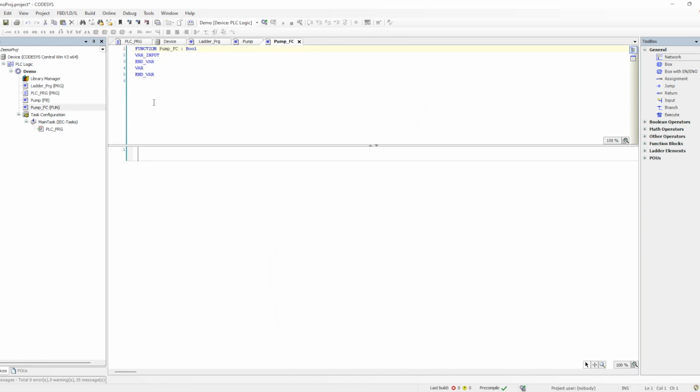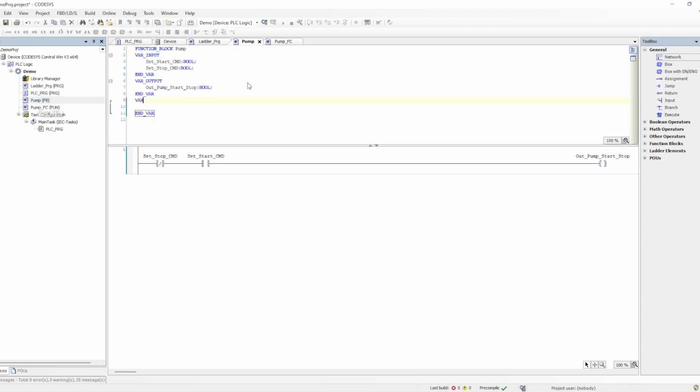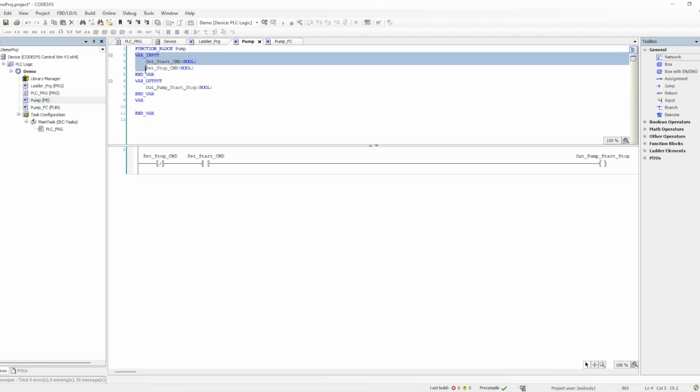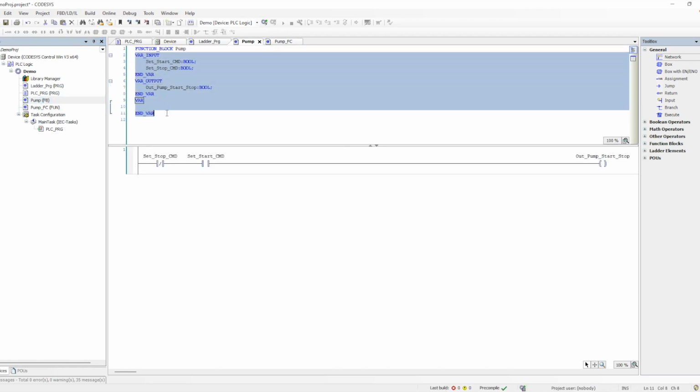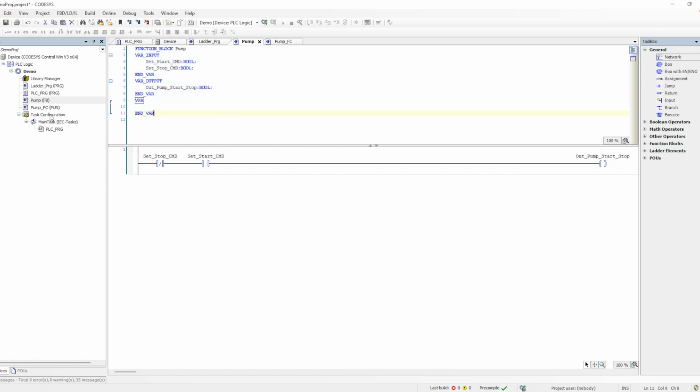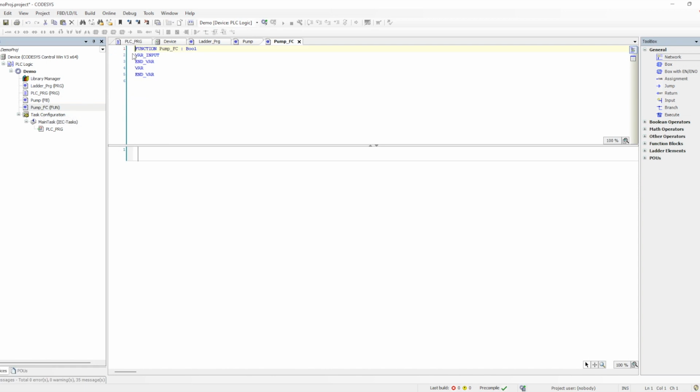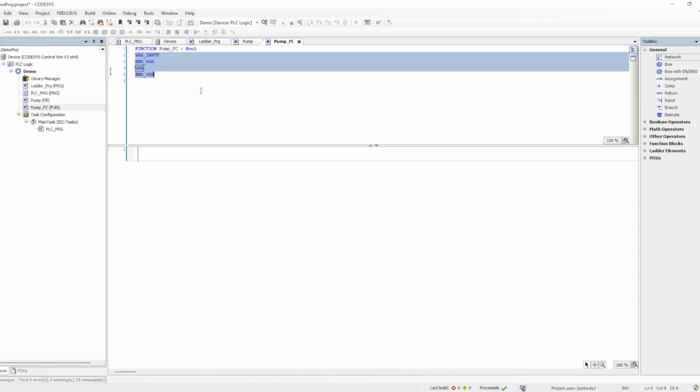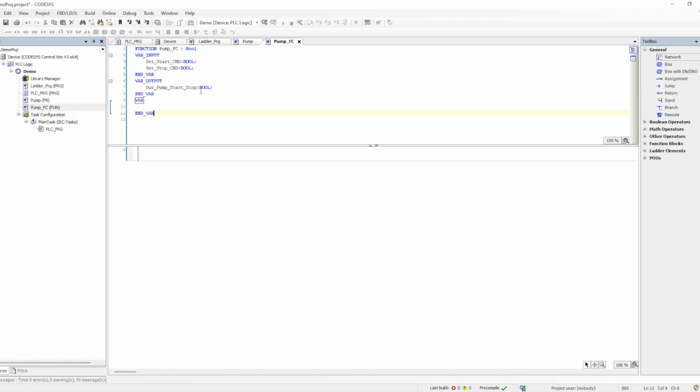A function block has its own memory, so when we go inside, it will show exactly how that particular instance is running. But for the function, when it is called, it gets executed, and then there is no memory for that. So we will not see exactly, when we go inside, what the state of that particular function is at that time, because it is getting executed for all the calls where it has been done.